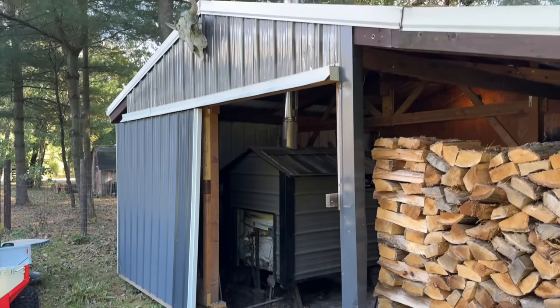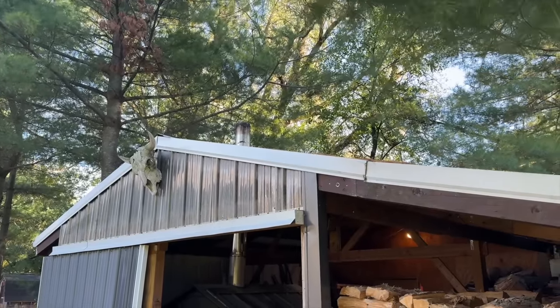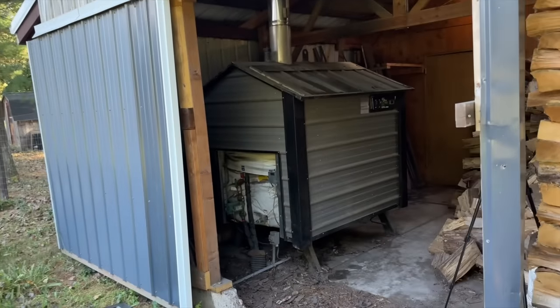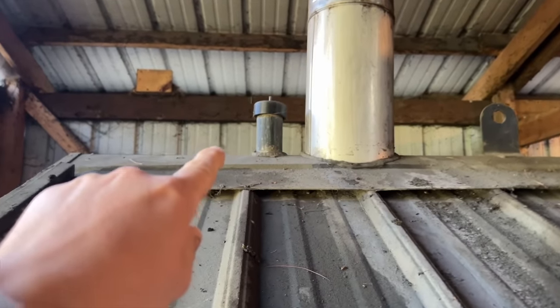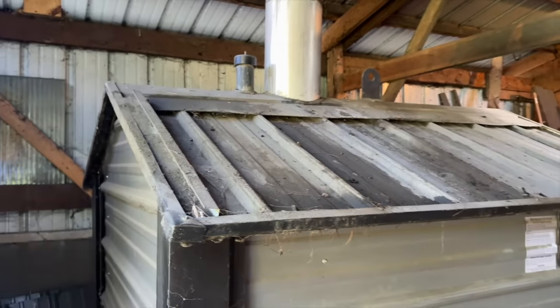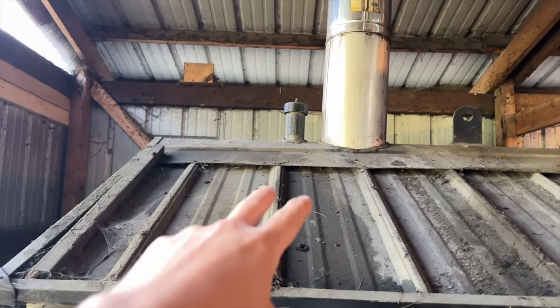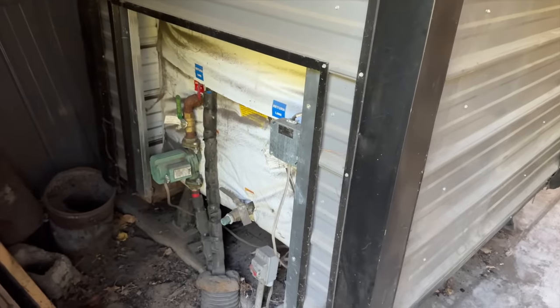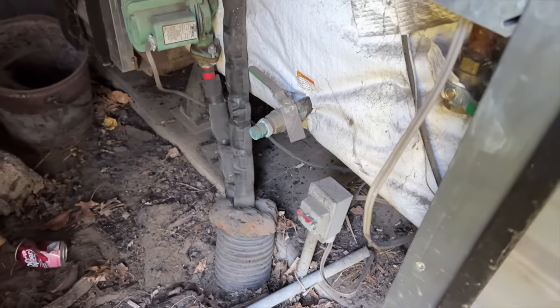I went ahead and did the few things that need to be done before firing this thing up. Number one, remove the cap on the chimney if you put one on — which you should have on during the summer to prevent rain from going down your stack. The other thing I did is I topped off the water: take that little cap off and run water in there. Once the fire gets going and that water heats up, it is going to expand and cause some of that water to flow out that cap. Then I just flip that switch.